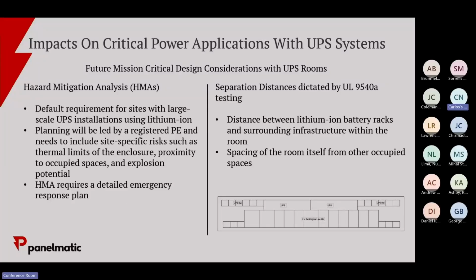So if you're having a dual UPS system, 12 or 1600 kW, you could put 2, 6, or 9 racks of batteries on the end, and now you're just doing conditioning, fire suppression, and gas detection in that one room versus having to do the whole thing. You could still leave them in this configuration, but then you've got to run gas detection and fire suppression through the whole thing, and circulate enough air throughout. It's a lot more expensive to do. This is a big deal for all the modular manufacturers.